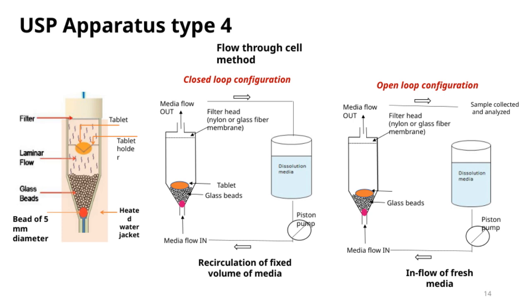First, we have the heated water jacket, which is essential for maintaining a consistent temperature during testing. This helps ensure the accuracy and reproducibility of our results. Next is the tablet holder, designed to securely hold the tablet in place within the apparatus.